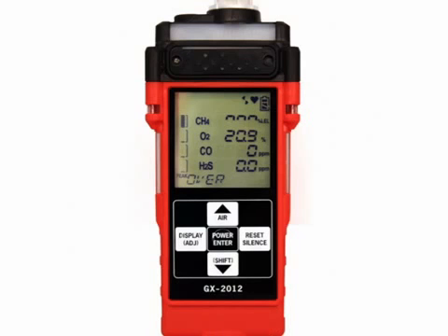Follow your established procedure for an increasing gas condition. Reset the alarm using the Reset Silence button once the alarm condition has cleared. Calibrate the GX2012 as described in the calibration section of the manual. If the overrange condition continues, you may need to replace the sensor that has triggered the overrange alarm. If the overrange condition continues after you have replaced the sensor, contact RKI Instruments for further instructions.